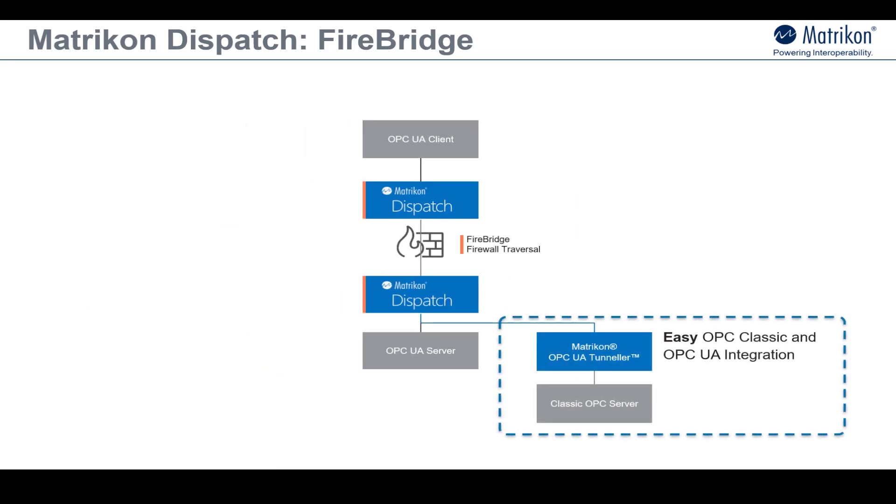You can also use Dispatch Firebridge functionality in architectures where your OPC clients and servers are still based on OPC Classic. You can do this by using the Matrikon OPC UA Tunneler product which enables communication between any combination of your OPC UA and OPC Classic components.